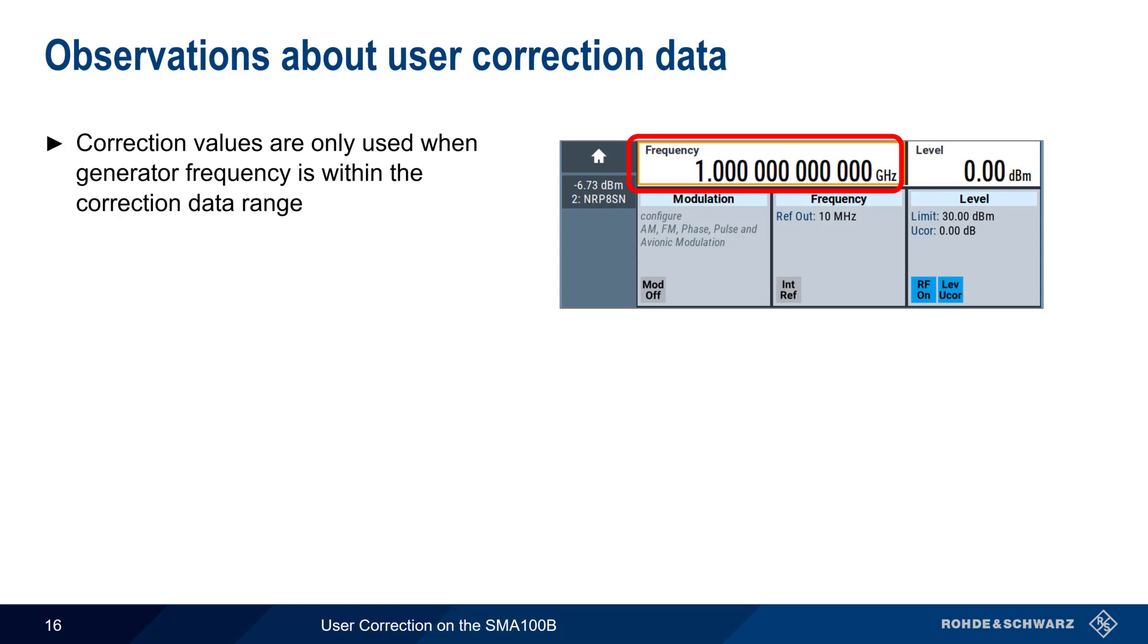Before we wrap up, a couple of quick observations about using correction data. First, remember that correction data is only used when the generator frequency is within the range of activated correction values. If our correction table covers 700 to 800 MHz, and our generator is operating at 1 GHz, no user correction is possible.